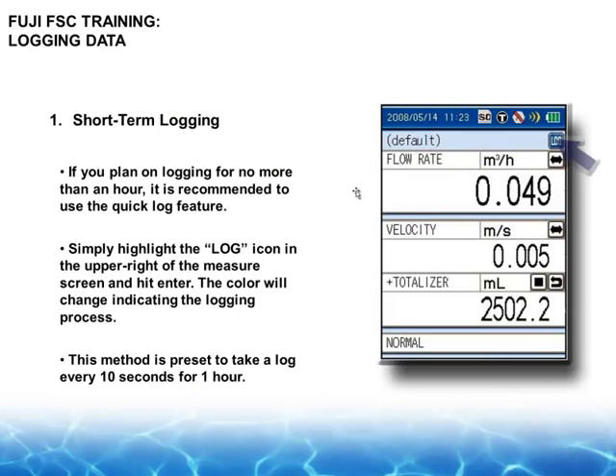Now the logging, this is in the way cool category, as my daughter says. I can't say that anymore, I'm too old for that. If you're up on the ladder and you say, gee, I sure wish I brought a pencil and a notepad to jot down what I see on the display, all you need to do is press the log button and it will take a screenshot and save it. So we're now talking laptop functionality with this device. And that data is saved on your SD card.